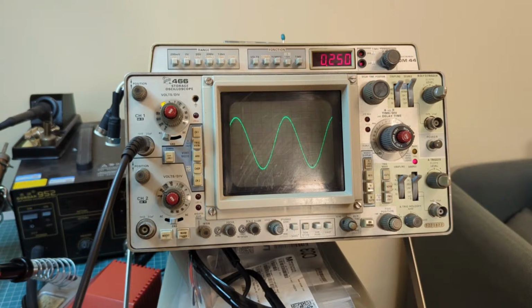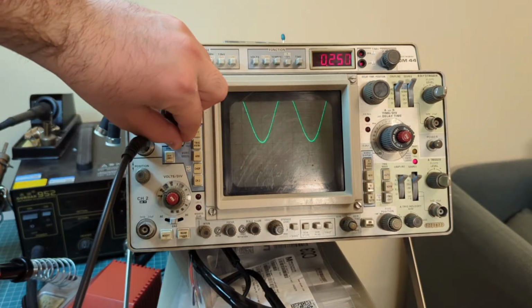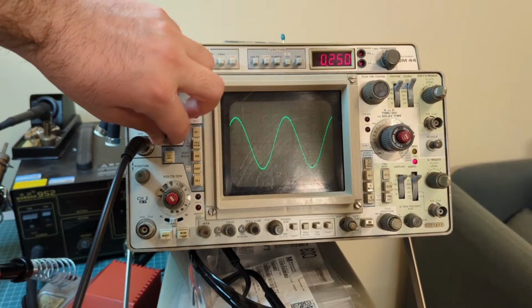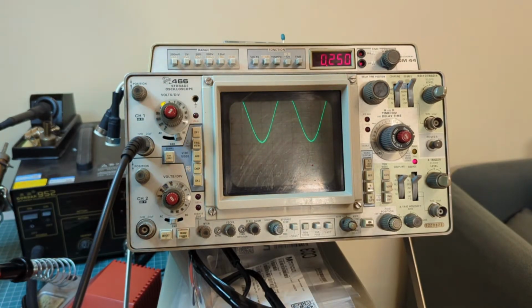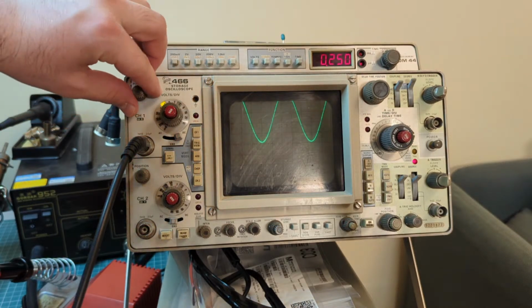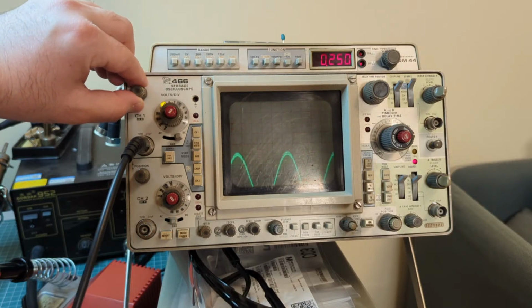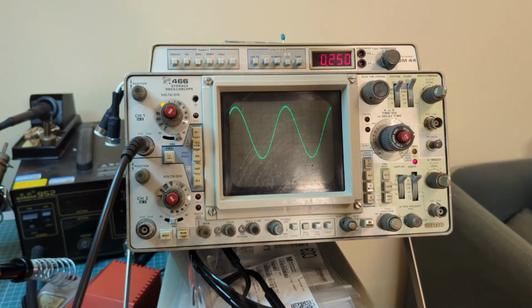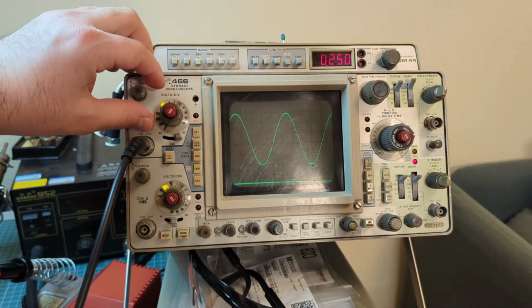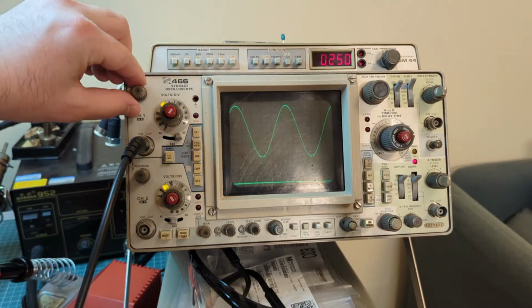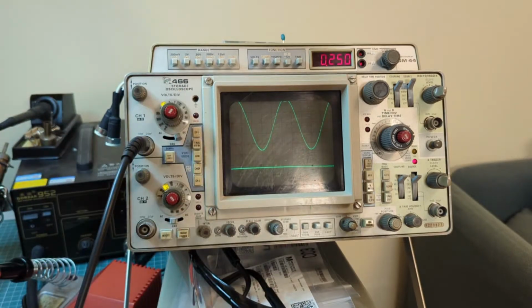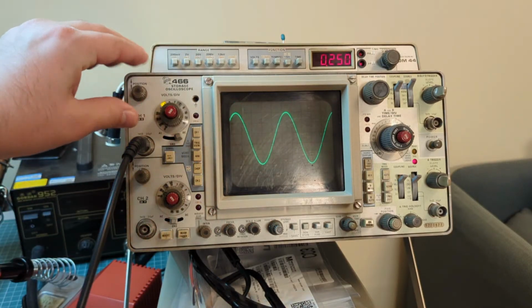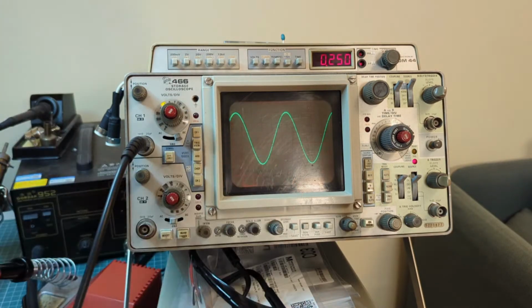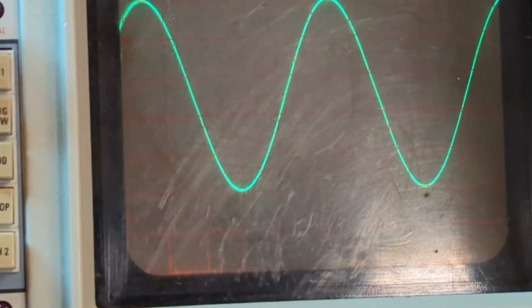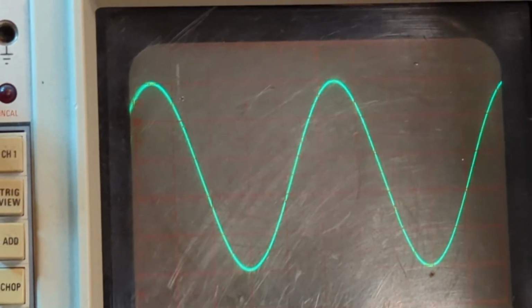So yeah, let's go back to the vertical section. So far we've discussed coupling, and I hope this is clear for anyone, and you can see what it's doing here because we have a signal that has an offset. Okay, and now there is another adjustment here that's really important, which is the vertical position, which is probably self-explanatory. This one just allows you to shift the signals up or down, and this would be useful in many cases. For example, if you have two traces, maybe you want some separation between them, so you want channel 1 to be shifted upwards so that you have room for the other trace or something like that. Another use case would be, even for a single channel, if you want to measure the amplitude, especially on an analog scope, then you want to align the signal with the graticules so that you can measure the amplitude, and this is where the vertical position comes in handy.